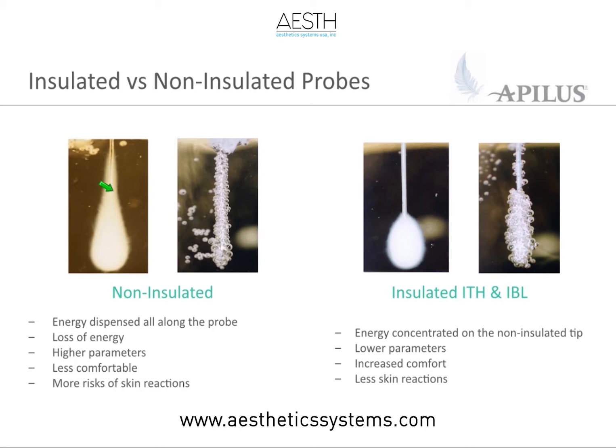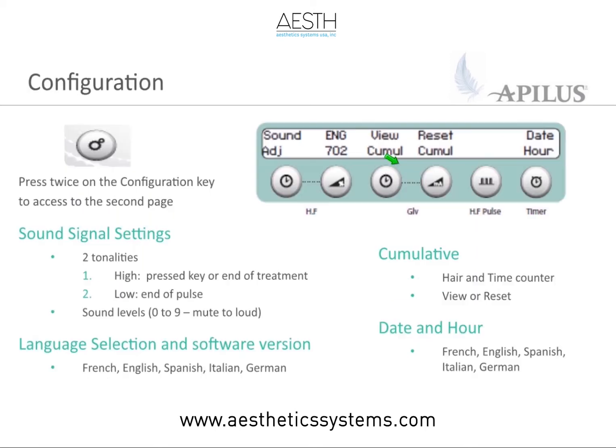It takes into account loss of energy higher up in the probe where you don't see something like that happening with insulated probes. Insulated probes, you have the insulation here, forcing the current to come out of the non-insulated portion of the probe. So that allows you to lower your parameters. Because the parameters are lower, the setting is going to be more comfortable for the client. Because you're protecting the top of the skin, you will see less skin reactions happening.